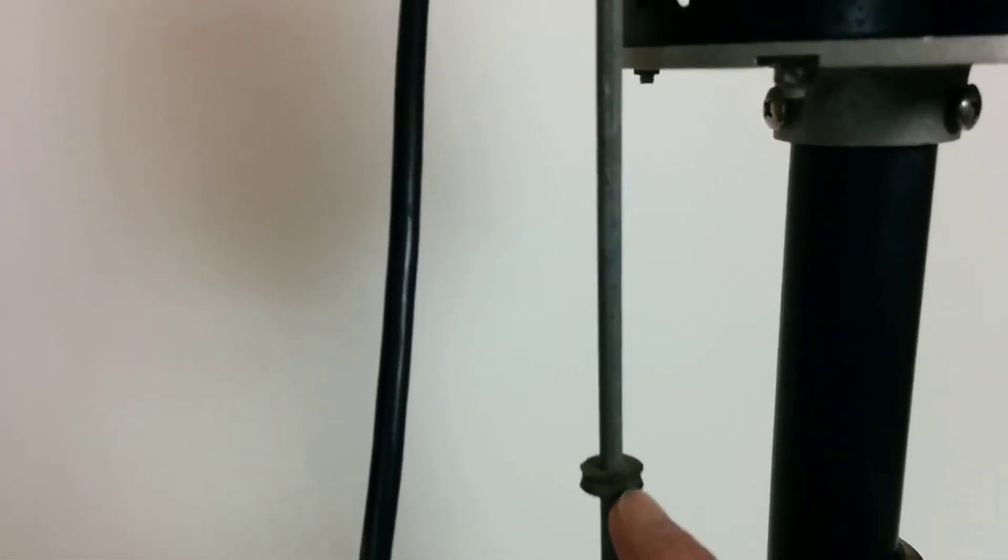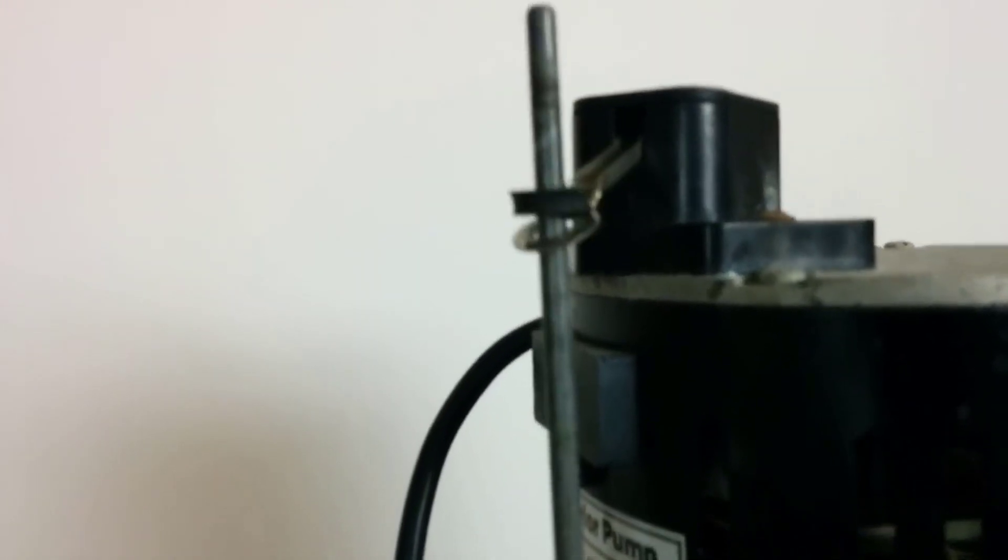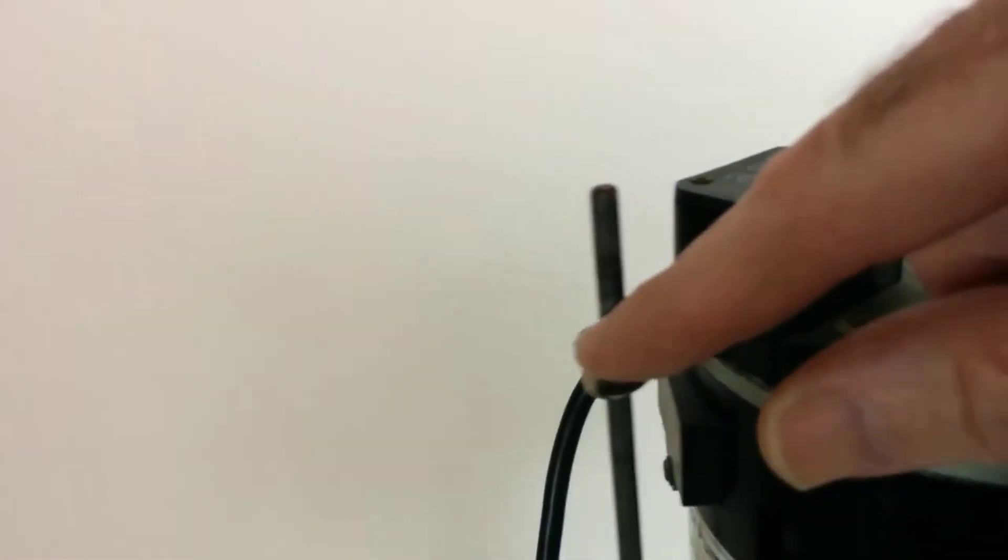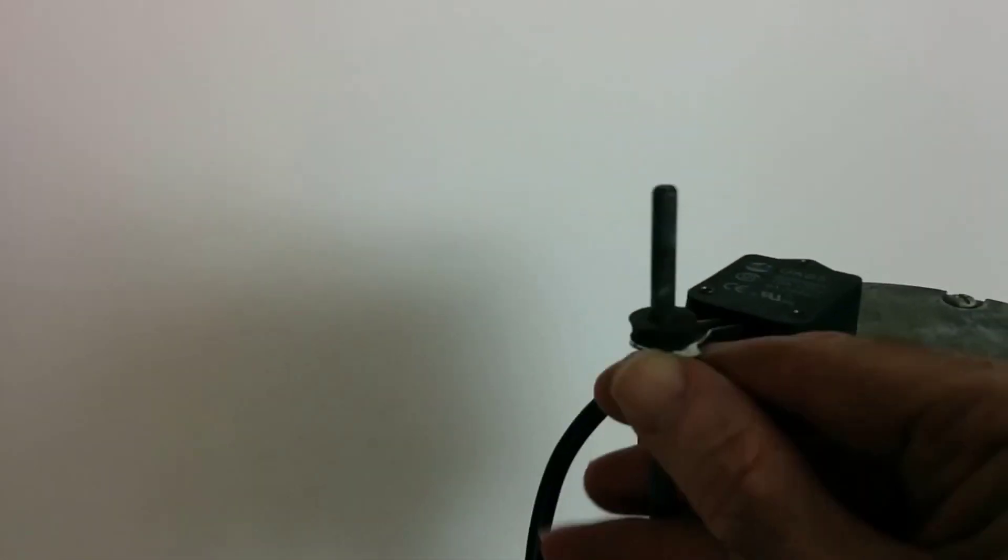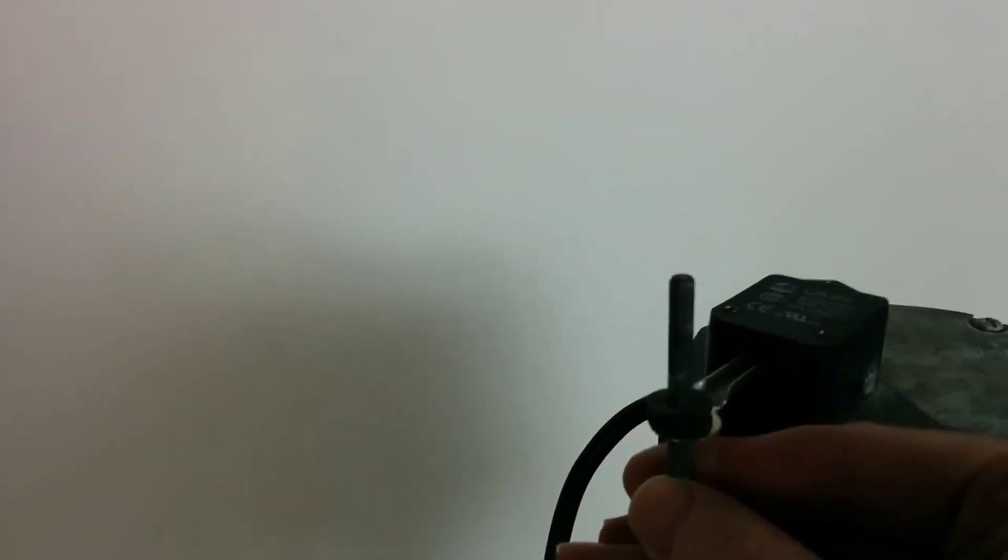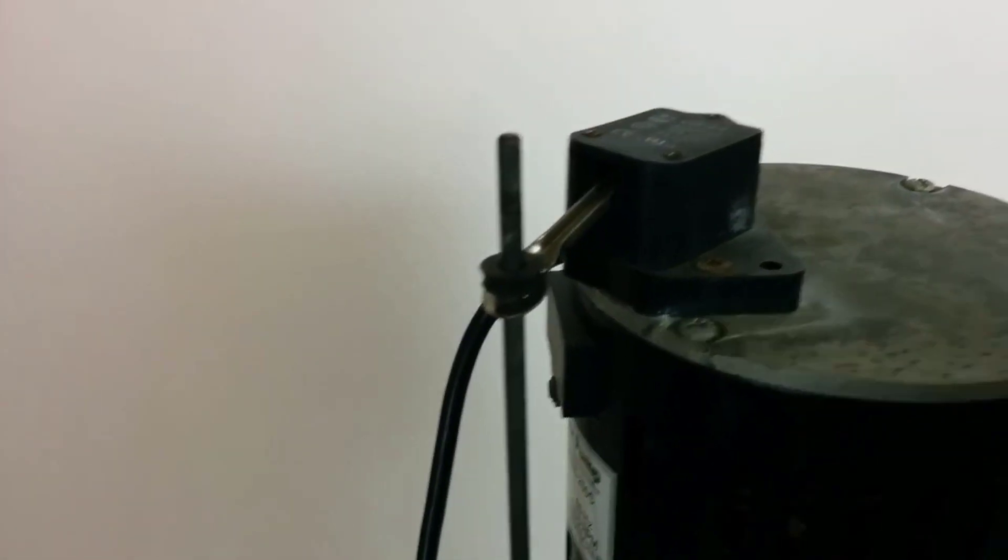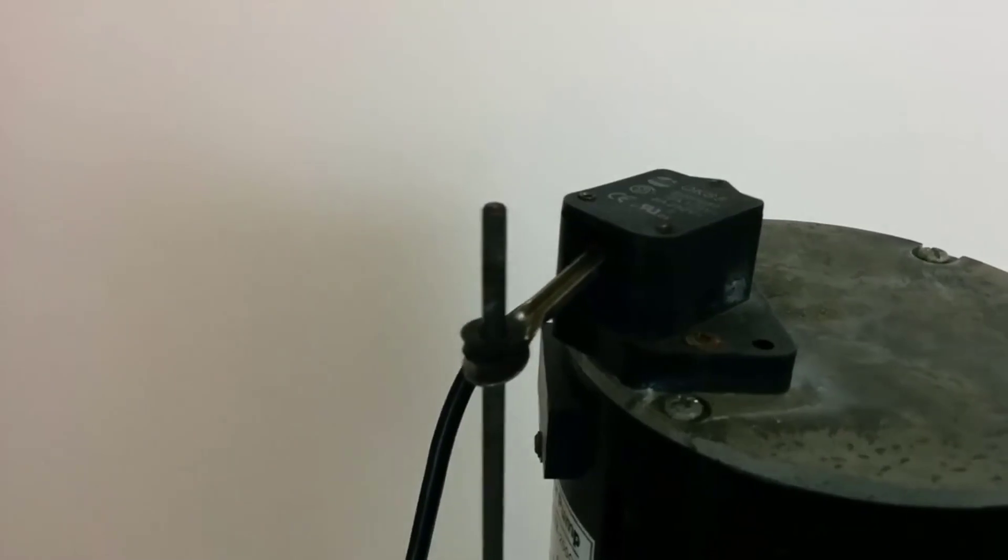Now I'll show you what happens where the switches are. This black rubber ring, this is what's going to trigger that switch up here. Watch what happens, I've got it plugged in. So here we go, we're lifting up, there's your black rubber ring, comes up like this. Now see, that one shut it off, so the switch is in the up position like that. Once that float drops back down, that's what shuts off the switch.